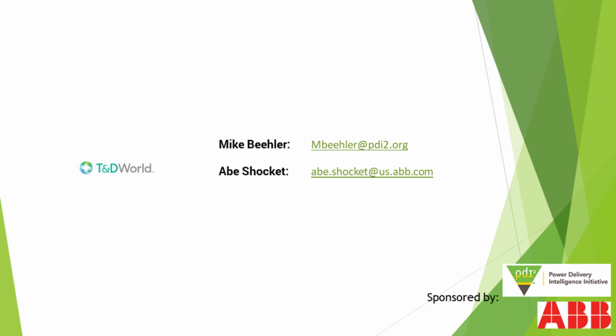Particularly these days with distributed energy resources, we hear a lot of requirements for 25 kA: wind farms, 38 kV with 25 kA, data centers. So there's all kinds of growing, difficult requirements, and different manufacturers make solid dielectric switchgear that can accommodate different ratings. I do admit that my own ratings chart has some holes in it. I can't hit every rating at every voltage, but in general, it is something to discuss with your supplier upfront because it might drive some requirements around space and availability of the gear.